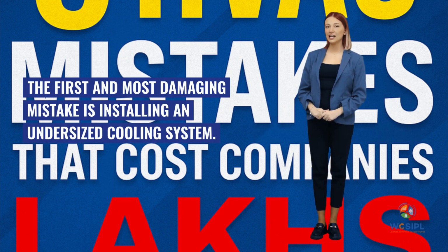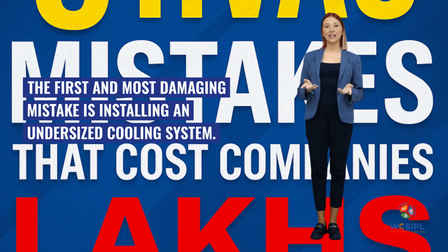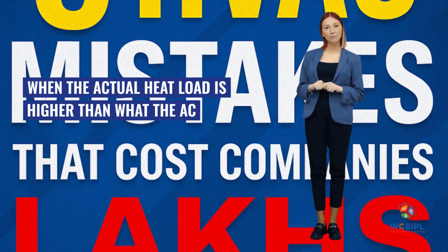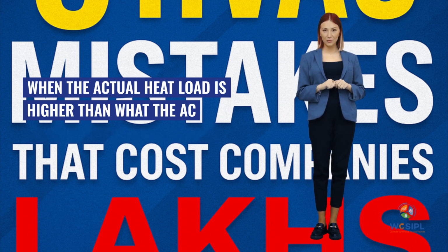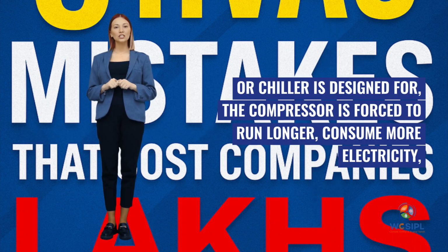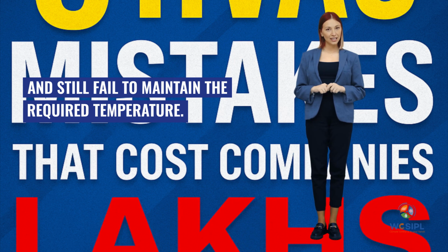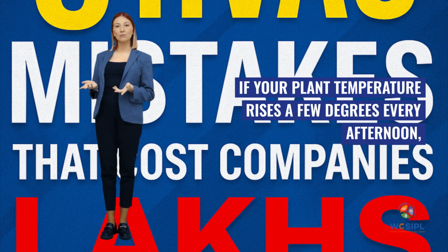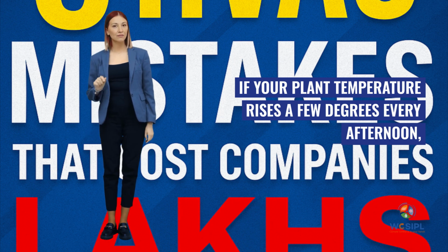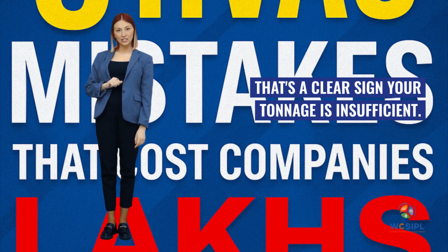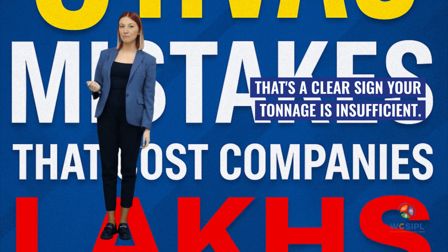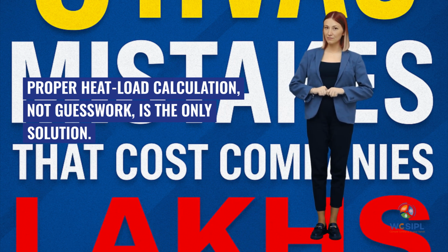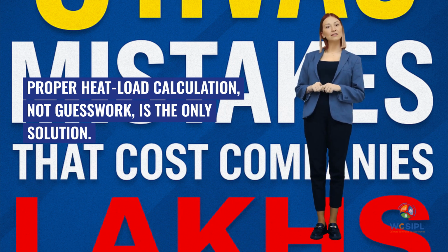The first and most damaging mistake is installing an undersized cooling system. When the actual heat load is higher than what the AC or chiller is designed for, the compressor is forced to run longer, consume more electricity, and still fail to maintain the required temperature. If your plant temperature rises a few degrees every afternoon, that's a clear sign your tonnage is insufficient. Proper heat load calculation, not guesswork, is the only solution.